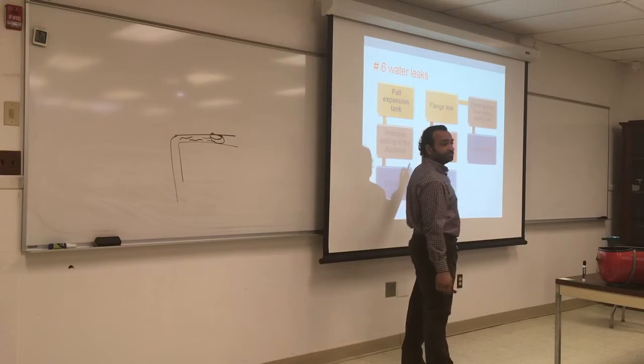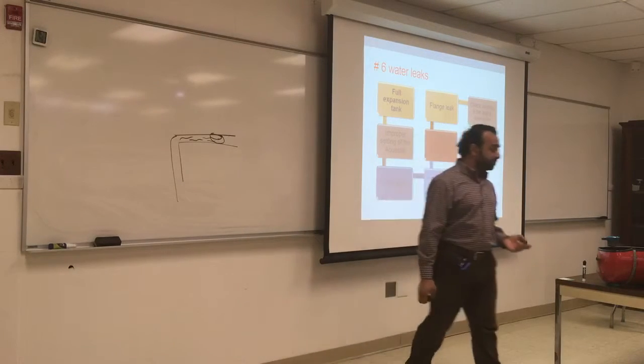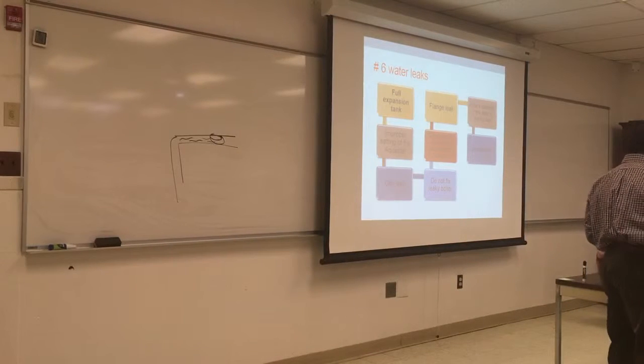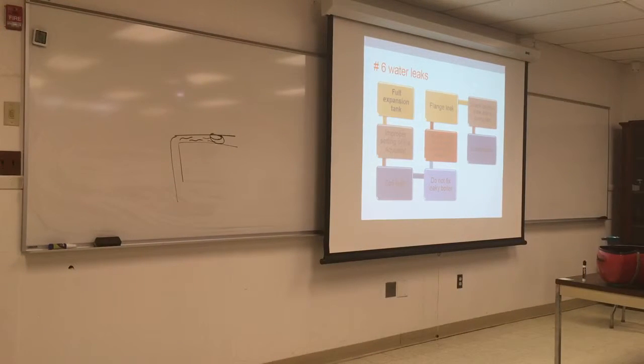The flange. Pumps have flanges and bushings. If you think about it, this is a circulator, this is a motor, and this is the pump part. If you think closely, there's a shaft going from the motor to the impeller. There's water in here, and there's no water in here.